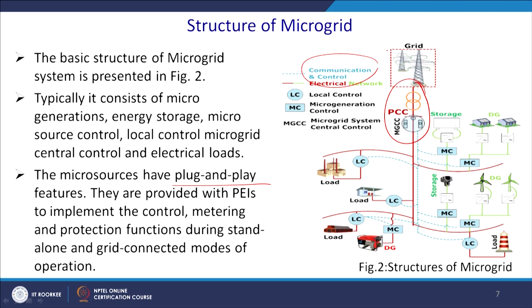You may connect this point to the grid to exchange power. Once you have a surplus in the microgrid, you can sell it to the grid, or if you have more load demand, you can take it from the grid, or you may operate in islanding mode. So, that also comes under the MGCC operation. So, for the microsource controller, operation and management of the microgrid in different modes, controllers are coordinated through the local microsource controller and the central controller. We may have a distributed controller and may have a centralized control.